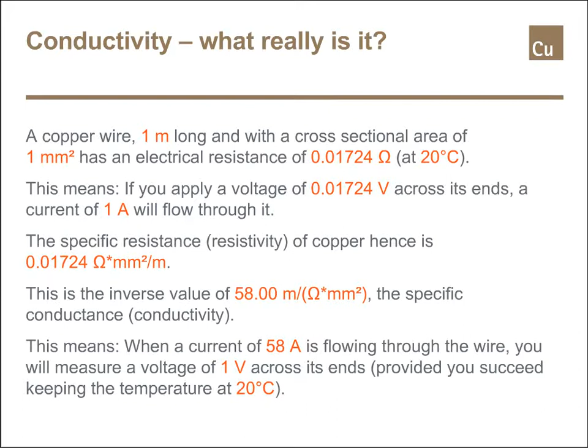The inverse value of that is 58 meters per ohm and square millimeter, which is the specific conductance or the conductivity of copper. This means the other way around, when a current of 58 amps is flowing through the wire, you will measure a voltage of 1 volt across its ends. This is a theoretical experiment because you would need to keep the temperature at 20 degrees Celsius while carrying out this experiment, and that may become difficult.